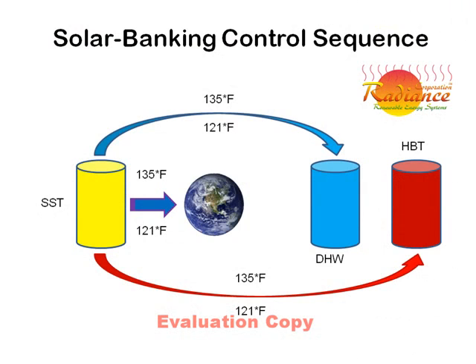Radiance Corporation implemented a solar banking system, integrating the geothermal and solar thermal heating systems. Excess heat from the solar thermal system is sent to the domestic hot water tank, the radiant heating buffer tank, and to the ground loop heat exchanger. This solar banking approach continuously sends solar heat where it will be needed next. It synergistically increases the efficiency of both the geothermal heating system and the solar thermal system in unison.